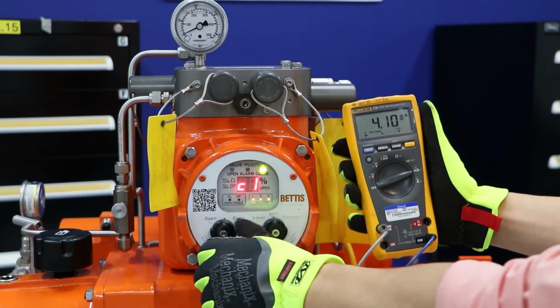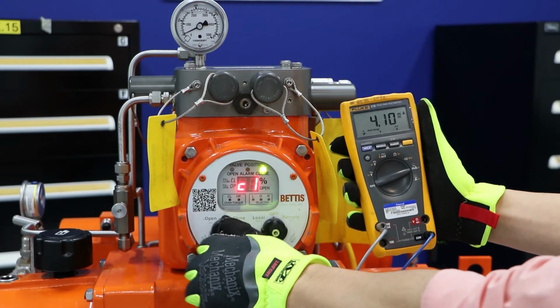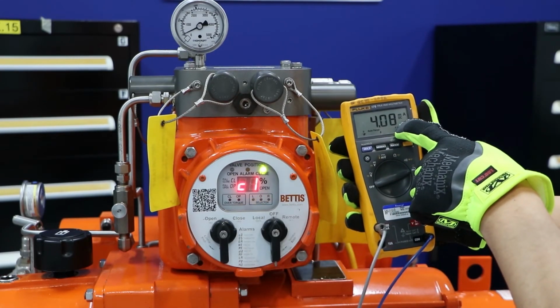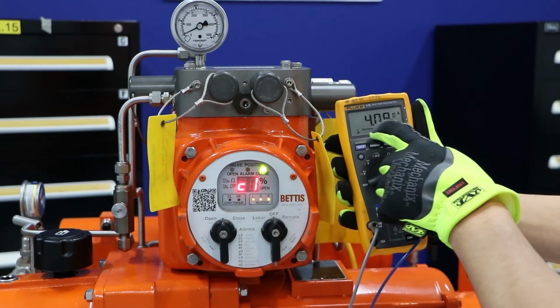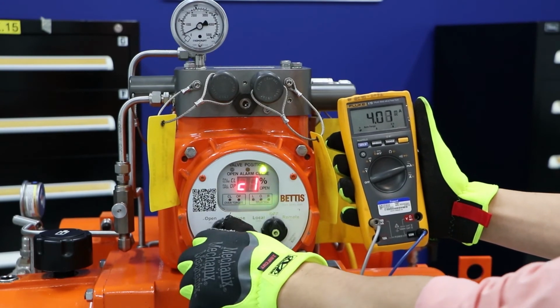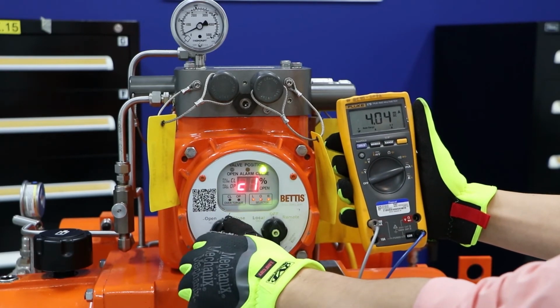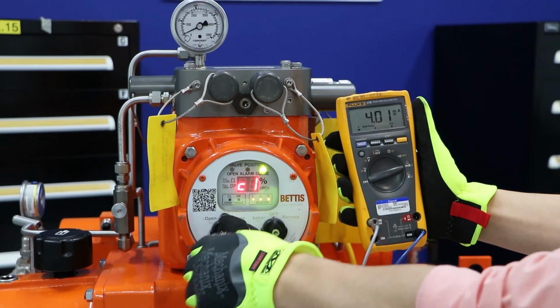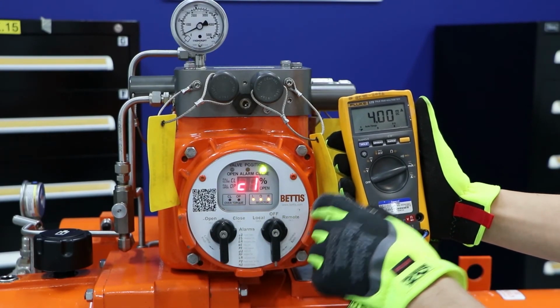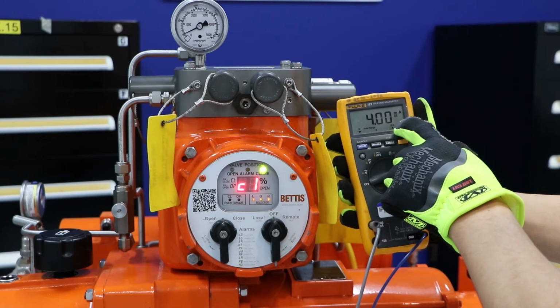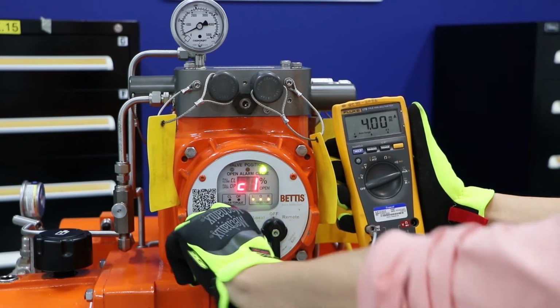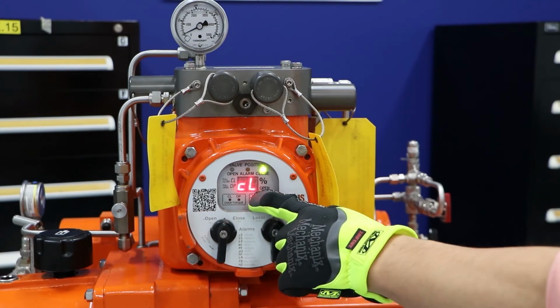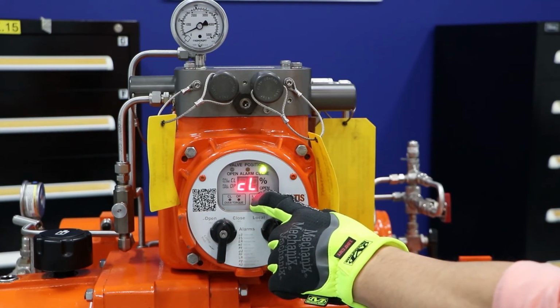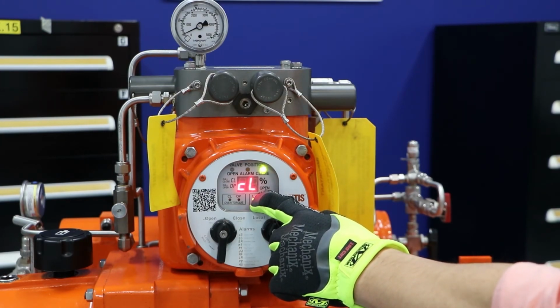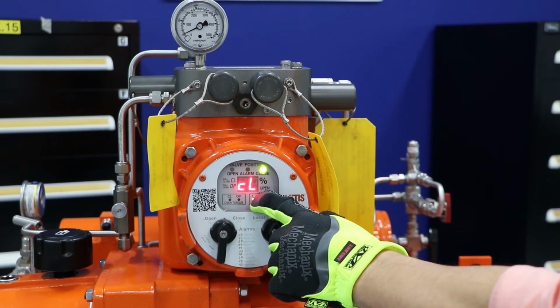So watch your multimeter as I select no. You'll see the value decrease. So we want to decrease this value to 4.00. Now our multimeter reads 4.00 milliamps. We toggle yes. Now we read CL. CL means we've successfully set our analog output for our lower limit. If it reads CF, that means we failed to set our lower limit, and you need to redo this again.